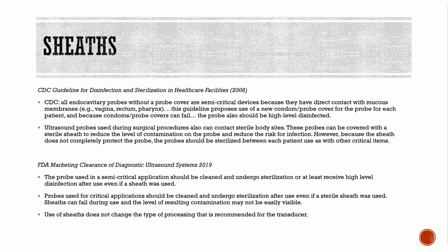One of the things that I've come across is that people don't always know that there's sheaths available, or they want to use something else. I have seen the probes be put into a sterile glove to meet this cover, or they'll put a Tegaderm over it. Neither of those are really meeting the intent of protecting the patient. It's really just a stopgap measure. So making sure that sheaths should be used, and regardless of whether the sheath is used, the probe still needs to be appropriately high level disinfected or sterilized.